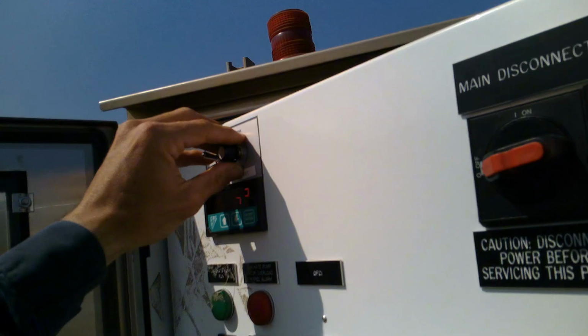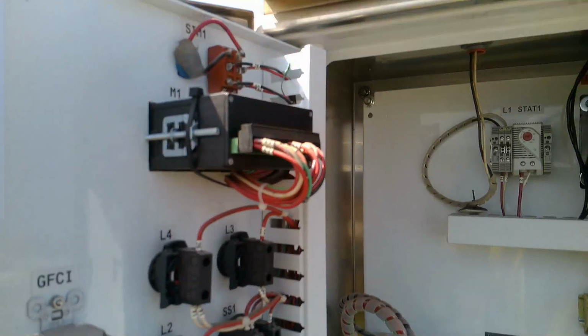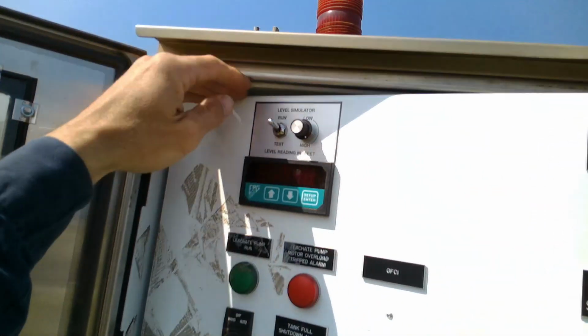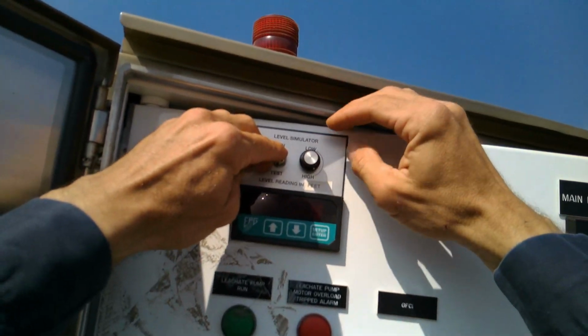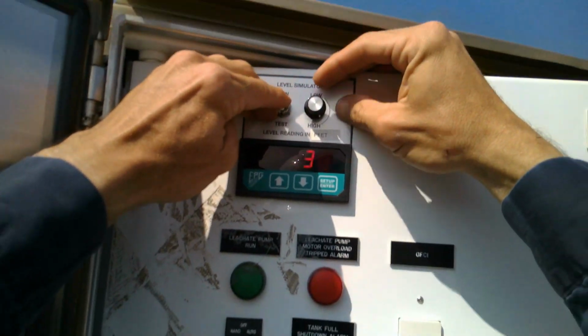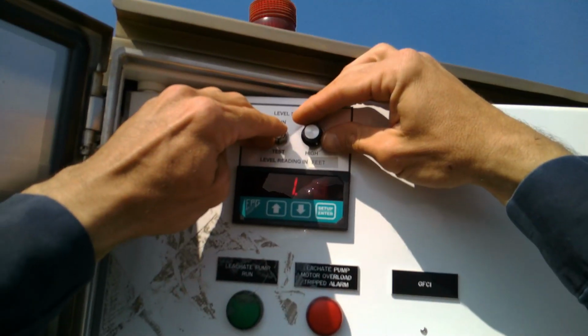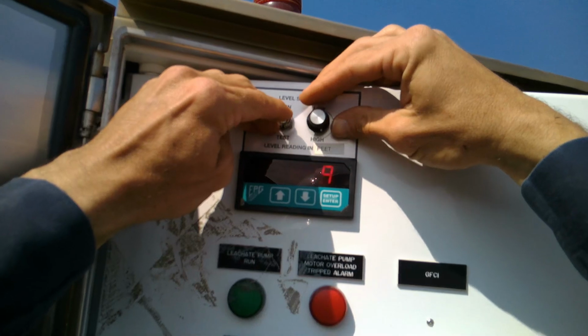You let the bypass, basically it's a little potentiometer, just resistance circuit that bypasses the transducer, so you can test your scaling there. We'll do it one more time. So put it in test mode. It thinks there's 1.37 feet. It's supposed to come on at 3.8, so we'll slowly turn it up.